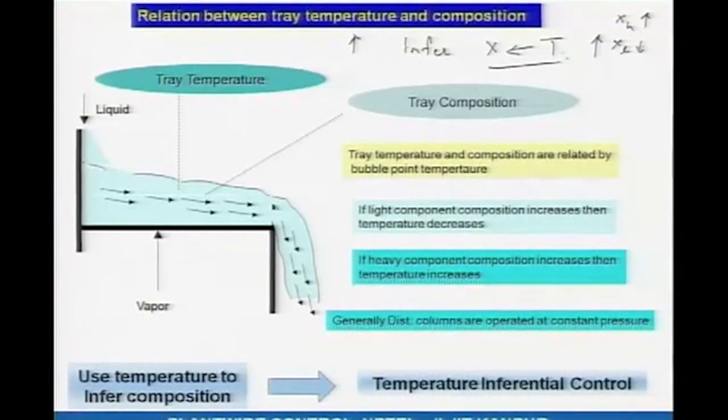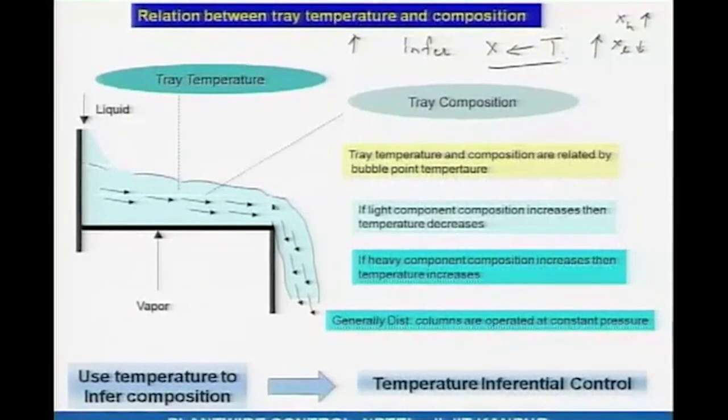Because composition measurement is quite cumbersome, you need a measurement of temperature that would indicate composition indirectly. Temperature measurement comes in really handy — most columns infer composition from temperature. If on a tray the composition of the heavy component is increasing, you would expect the boiling temperature of that liquid to go up. Similarly, if the composition of the light component is increasing, the boiling temperature will go down. So if the temperature is increasing, that indicates either composition of a heavy component is increasing or composition of a light component is decreasing.